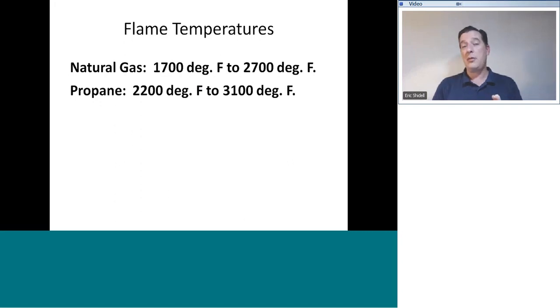This is interesting. Remember I said BTU and temperature aren't the same thing. Propane has about 2.5 times as much caloric value as natural gas does. However, the flame temperature certainly is not 2.5 times higher. It's absolutely not. It's a little bit higher, but really not a whole heck of a lot higher.